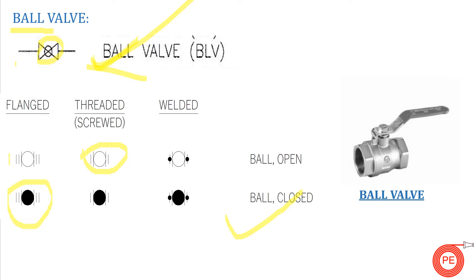For end connections on the ball valve: if two lines are shown across the valve symbol, it is a flanged type; if nothing is shown, it is a threaded type; and if two dots are shown beside the symbol, it is a welded connection. These connection indicators may differ slightly between designers or companies, but the basic valve symbol remains the same.